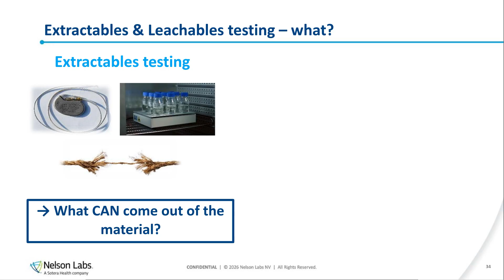So what is extractables testing? Extractables testing is testing what can come out of the material, as shown here. And then next up, we have leachable testing. And in leachable testing, you're more going to milder conditions, and you want to see what comes out of the material and into the patient. However, a problem with medical devices, of course, is that the application is within a patient or on a patient, and these conditions are very difficult to simulate in a laboratory. So we are going to call this simulated use conditions, as you cannot perfectly replicate the reality. So leachables or simulated use studies are part of extractables because the conditions are milder. You expect less leachables than extractables. But leachables in this presentation will not be a focus. It was just to explain what the difference is between extractables and leachables.